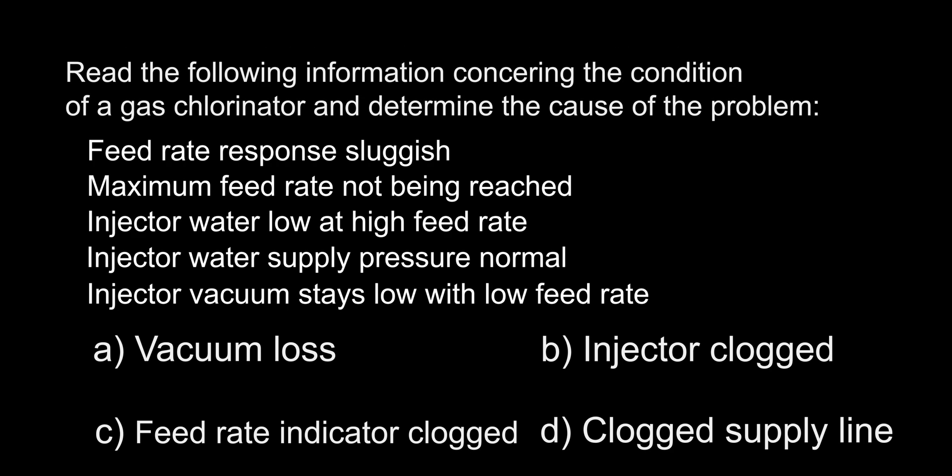Read the following information concerning the condition of a gas chlorinator and determine the cause of the problem. Feed rate response sluggish. Maximum feed rate not being reached. Injector water low at high feed rate. Injector water supply pressure normal. Injector vacuum stays low with low feed rate. A. Vacuum loss. B. Injector clogged. C. Feed rate indicator clogged. D. Clogged supply line.